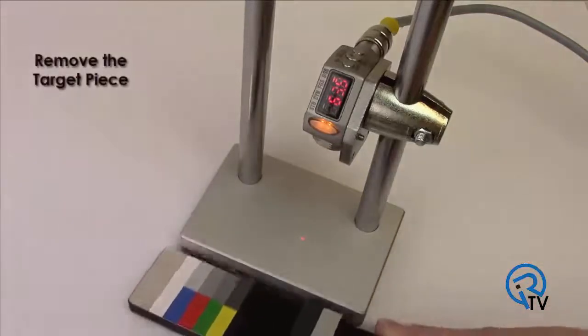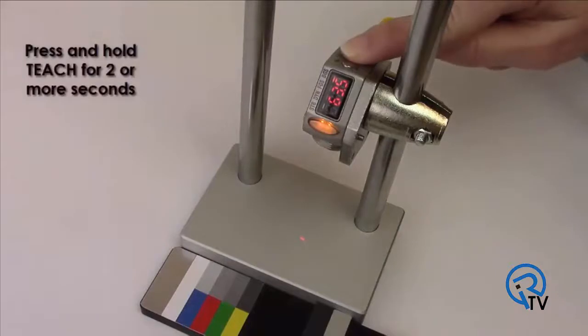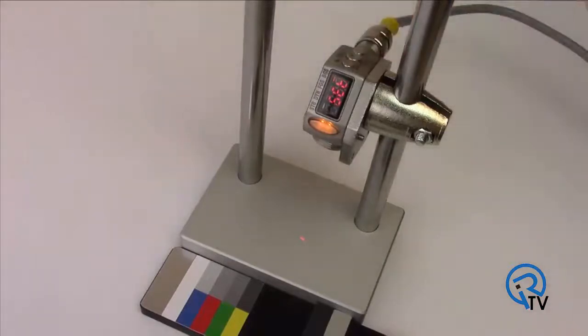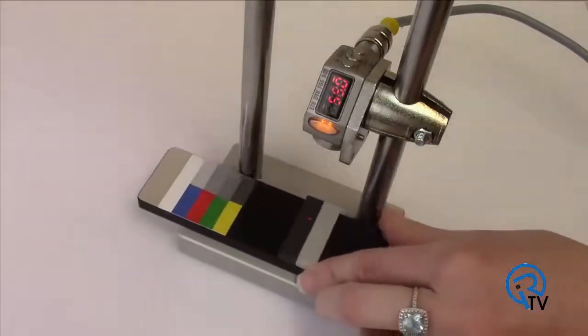Remove the target piece. Press and hold teach for two or more seconds. Then press teach again. The aluminum base is now the zero point. The sensor detects any part of the target but not the aluminum base.